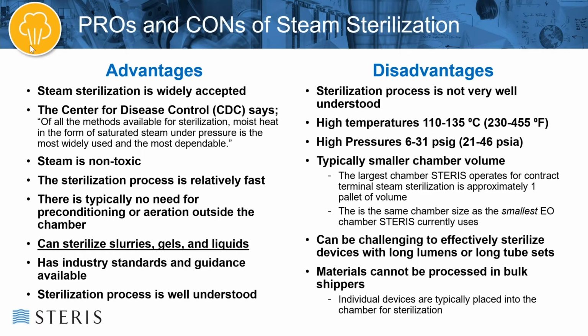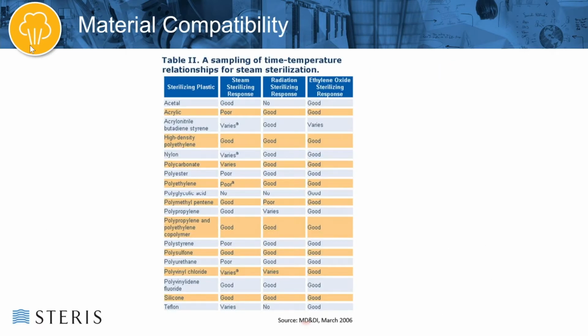Some of the advantages and disadvantages for steam sterilization relate to material compatibility. So some of you might have seen this table. I think I've seen it many, many times in a lot of different presentations. It's widely used. I'm referencing this from MD and DI, which was published in March of 2006, where they talk about material compatibility between steam sterilization, radiation, and ethylene oxide sterilization. So you can see that there are a lot of good items that can be processed in ethylene oxide. Material compatibility is very widely accepted for ethylene oxide. There's a couple of no's and some varies over here for radiation. And then for steam, there's a poor and some varies and a poor and a no. So it kind of goes from right to left as far as the number of materials in this particular table that are compatible with that particular technology.